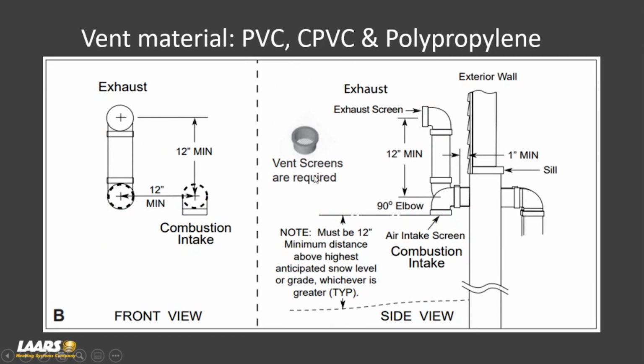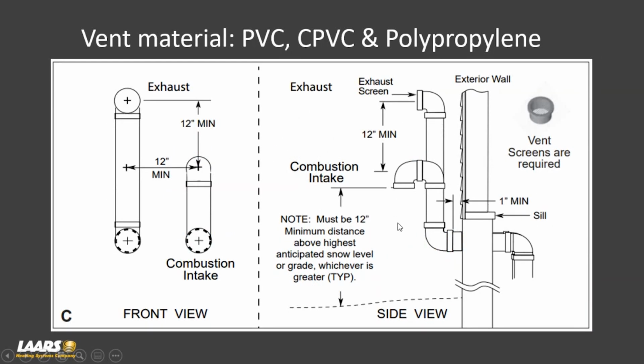All right. So hypothetically, if you want to come out and snorkel up, you can. So here's our combustion air intake. The suggestion is to snorkel up a minimum of 12 inches, and then straight out, not back down. Especially, again, flue gases are just going to recirculate. So on your snorkel, you want to be 12-inch horizontal and a minimum of 12-inch vertical. However, if you're in a climate with a lot of snow, maybe you're coming out a sill and you want to get above snow level, which you're supposed to consider, you can also gooseneck both the combustion air and exhaust up, okay? So again, minimum of 12-inch horizontal, minimum of 12-inch vertical.